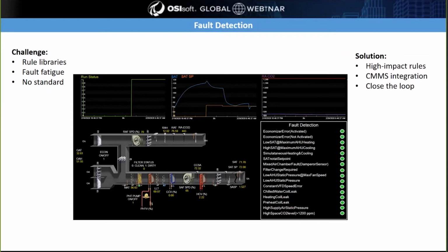The last point is closing the loop, where an analytics platform automatically makes changes to the automation system to correct errors. Before, we were creating a fault and generating a ticket, which is useful and valuable. But there's also a way to close the loop, where a fault can trigger a platform to make a change directly to your automation system.